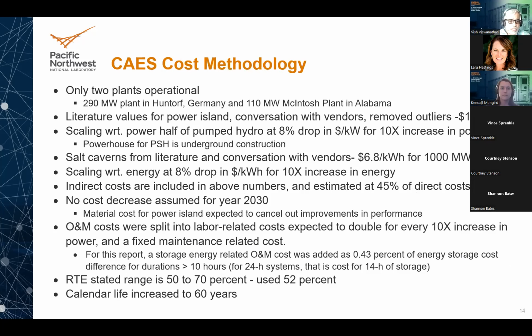For compressed air cost methodology, only two plants are operational. The literature review for Power Island cost is around $1,150 per kW, which also includes conversations with vendors. In terms of dollars per kW scaling, we had half the scaling compared to pump storage — 16% drop per order of magnitude increase in power for pump storage, versus 8% for compressed air — because there's no underground powerhouse construction for compressed air.